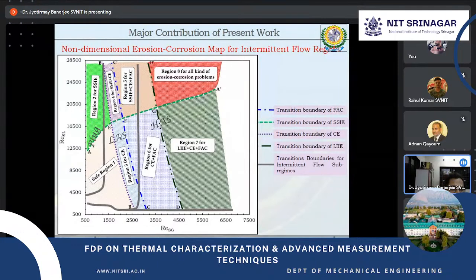But if you are operating in this regime, you expect cavitation erosion. In this regime, you expect shear stress induced erosion. In this regime, all kinds of erosion corrosion can happen, including cavitation erosion and flow accelerated corrosion. These flow accelerated corrosions are such that they can even break the protective layers.